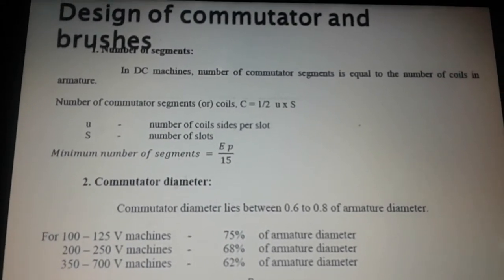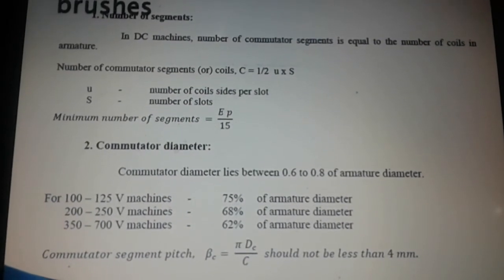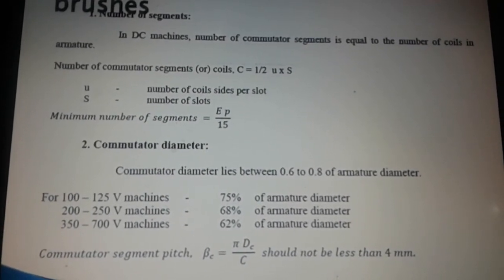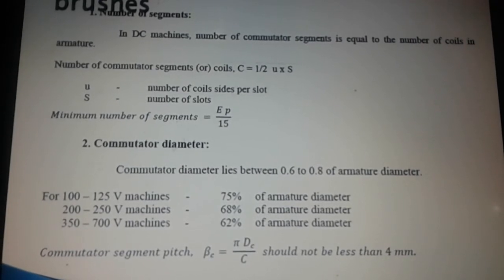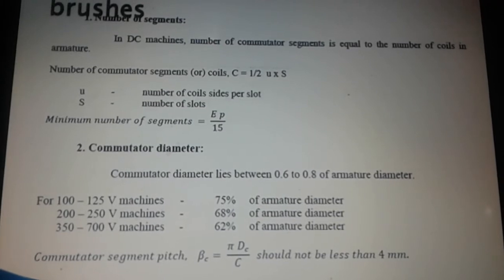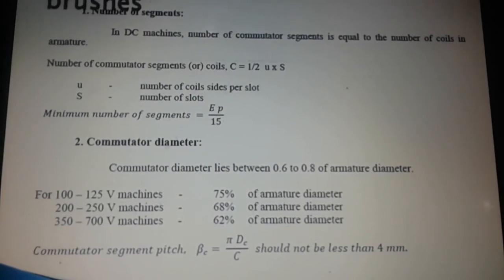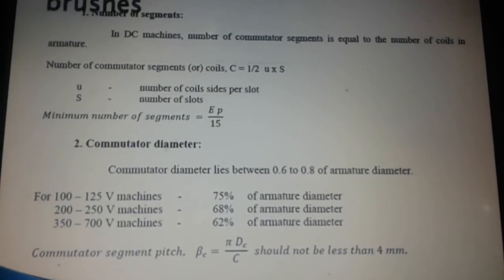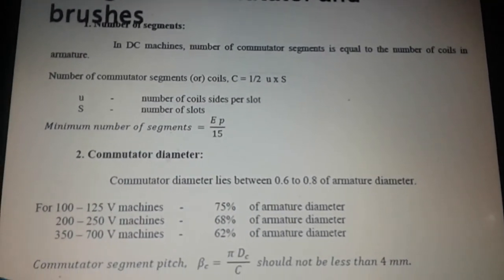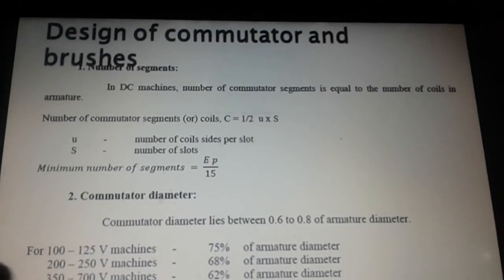Commutator diameter: The diameter of the commutator lies between 0.6 to 0.8 of armature diameter. The diameter of the commutator depends on the rating of voltage in the machine. For 100 to 125 volt machines, it is 75% of armature diameter.